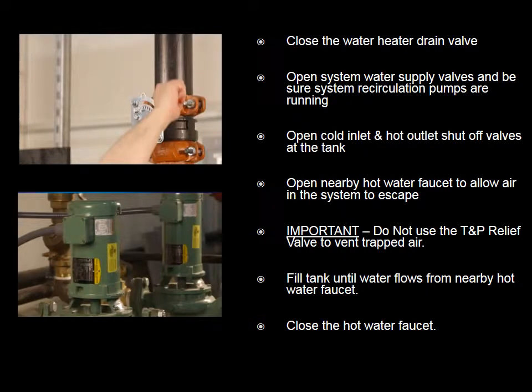With the drain valve on the water heater closed, be sure that all water supply system valves are open and that the system recirculating pumps are running. Next, open the shutoff valves on the hot water outlet and the cold water inlet piping to the unit. You will need to open a nearby hot water faucet to allow trapped air to escape when filling the storage tank. Using the T&P relief valve alone will not allow the tank to completely fill. A steady flow from the hot water faucet indicates the tank is full. You can now close the hot water faucet.